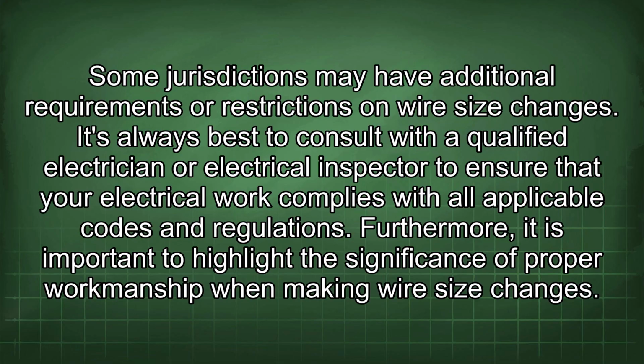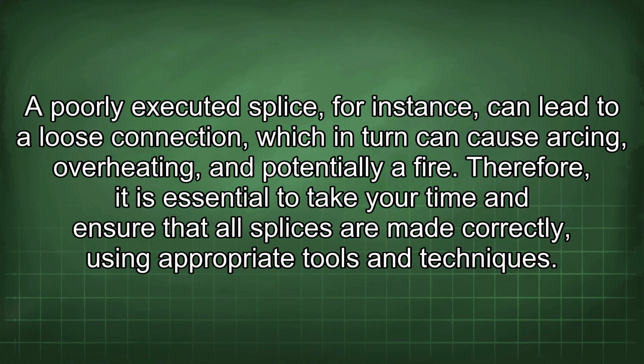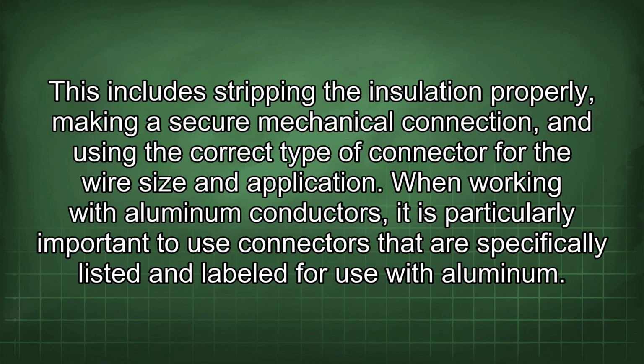Furthermore, it is important to highlight the significance of proper workmanship when making wire size changes. A poorly executed splice, for instance, can lead to a loose connection, which in turn can cause arcing, overheating, and potentially a fire. Therefore, it is essential to take your time and ensure that all splices are made correctly, using appropriate tools and techniques. This includes stripping the insulation properly, making a secure mechanical connection, and using the correct type of connector for the wire size and application.